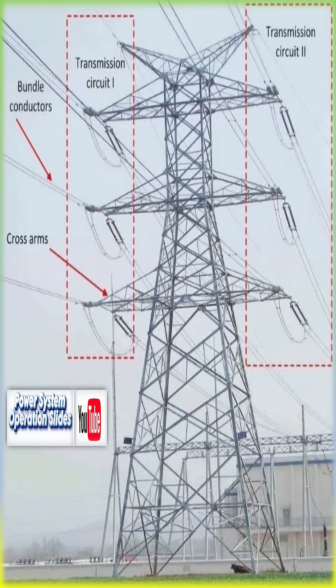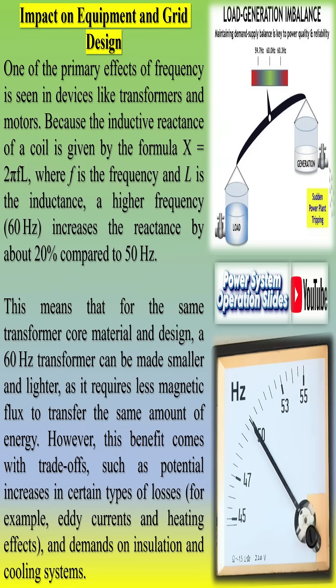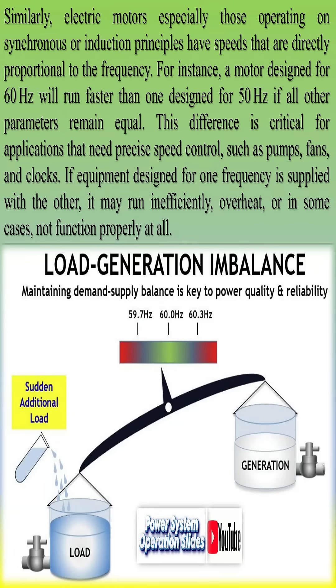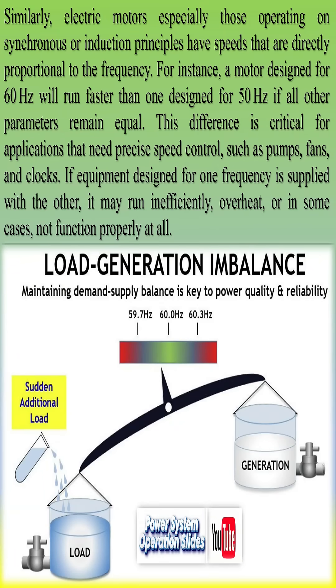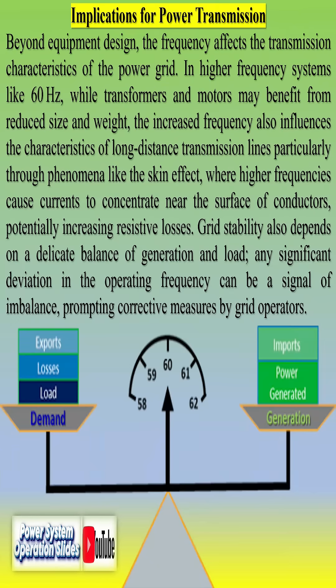Power lines are also affected by frequency variations. Higher inductive reactance X causes greater voltage drops along transmission lines, reducing transmission efficiency over long distances. As frequency increases, current tends to flow more on the surface of conductors — the skin effect — reducing the effective cross-sectional area for current flow, resulting in higher resistance in conductors and increased power losses in transmission lines at 60 Hz compared to 50 Hz.